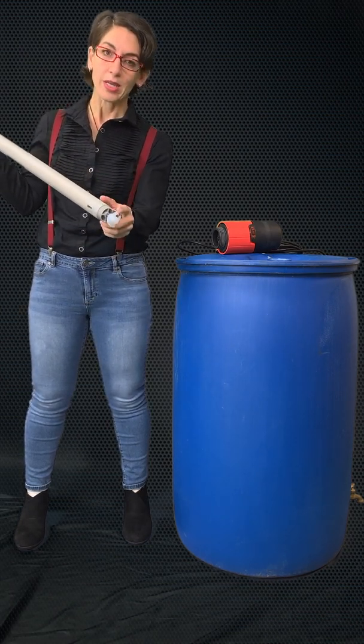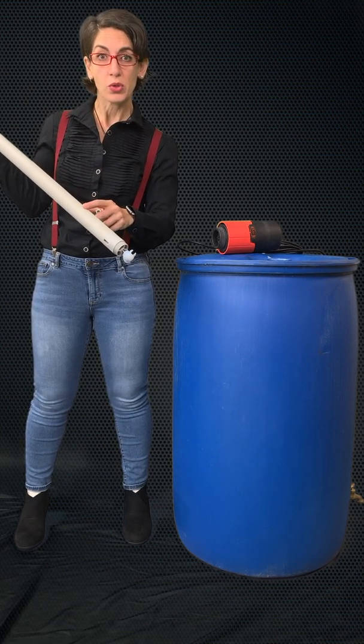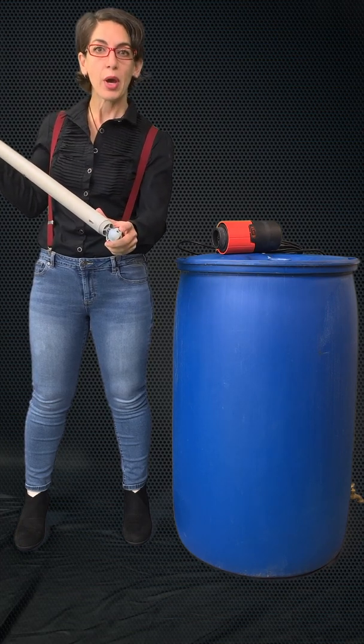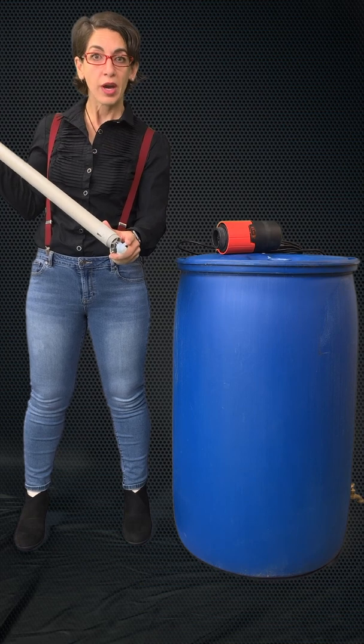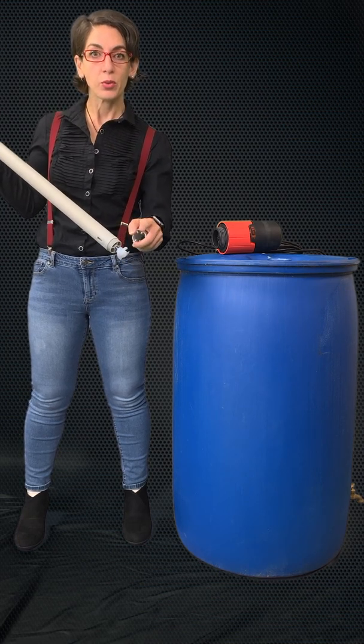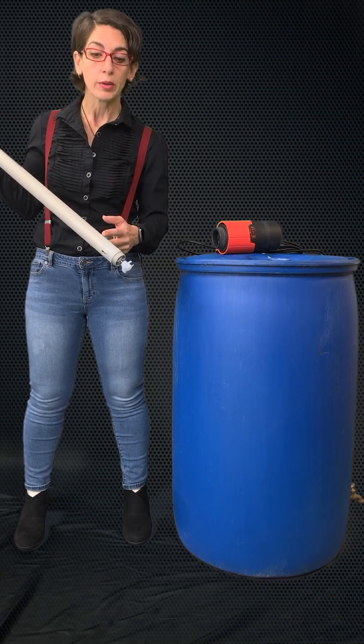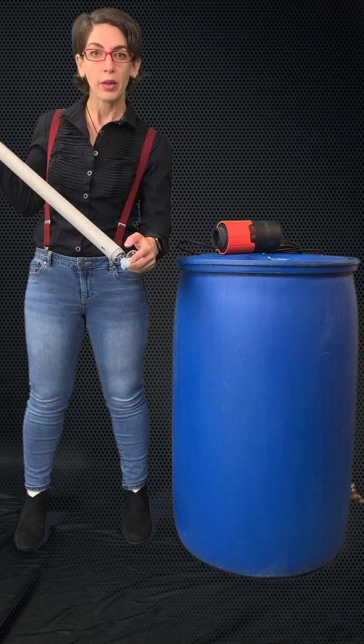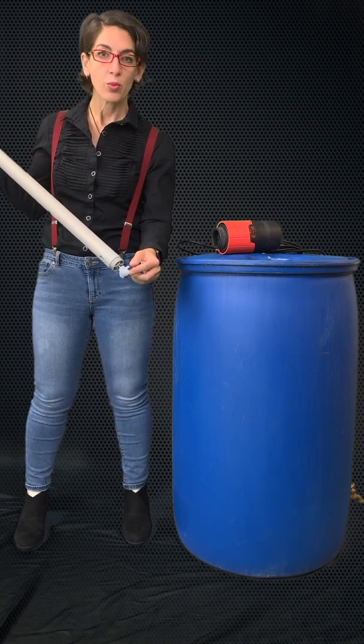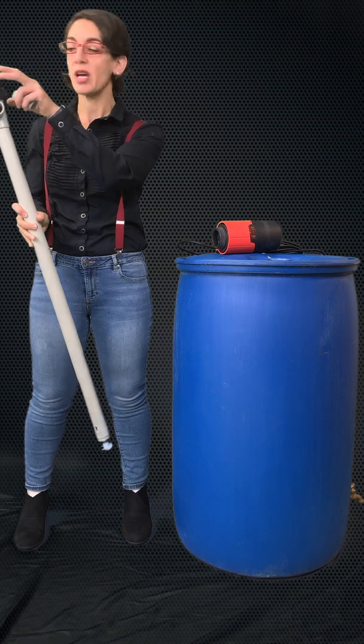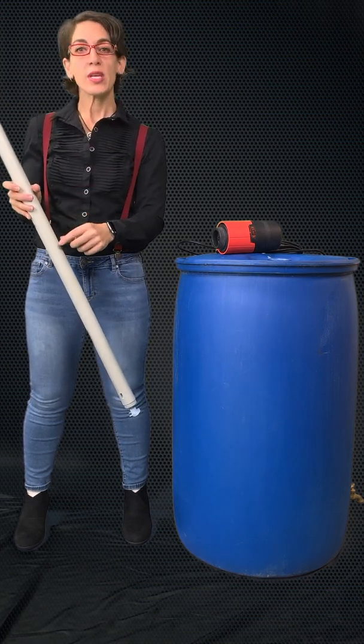And here is the rotor. You can see it's a different color than the tube itself. This is a European polypropylene, which is kind of like a cream color, but the impeller itself is an ETFE impeller. Most other manufacturers, the impeller is going to match the tube material itself. So in a polypropylene drum pump, some of them are blue out there, it would be a blue impeller. But again, Flux makes these pumps repairable. So besides the rotor, besides the coupling on the top and the union nut, the internals are repairable.